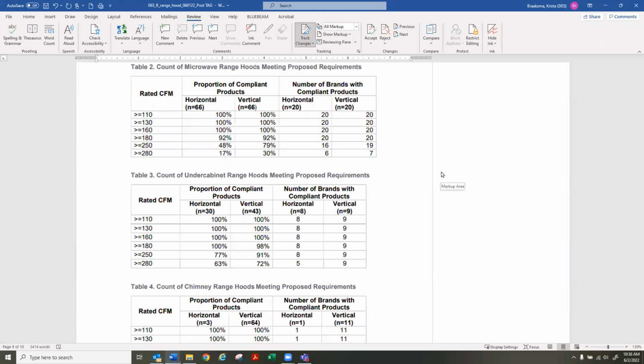So yeah, my comments kind of going back to the previous meeting, we did have some experts come in, Randy Cooper from AHAM and Ian Walker from Lawrence Berkeley Lab. One of the things I wanted to identify is that they stated that lab testing is still ongoing for these prescribed CFMs to see how effective this CFM is at mitigating issues for gas and electric. And Ian Walker from Lawrence Berkeley also identified that electric ranges, when you're frying and that sort of thing, still put out some particulate matter that's in excess of limits. It was also identified that the capture efficiency rating that was proposed is still not an official standard and is still under development. Also, Randy Cooper from AHAM identified that there is ongoing lab testing and ASHRAE is taking a look at some of these standards and working towards developing a standard.